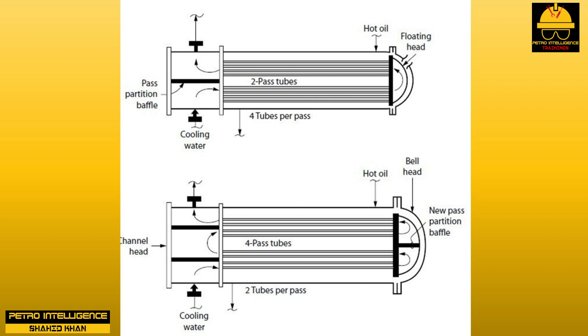The restricted water flow increased the water outlet temperature, the increased water temperature further reduced the water flow — a runaway cycle. They changed back to the two-pass configuration.